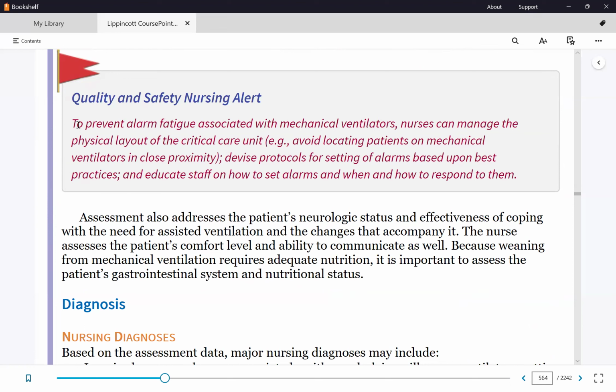During my time when I went to school, the vents were still capable of being... you can disable the alarm, and we can, because sometimes we're tired of hearing it. It's like the boy who cried wolf, it keeps beeping, but there's nothing wrong. The patient's absolutely fine. So we were able to disable the alarm. Now, modern vents, you cannot do that anymore. So you either have to fix the problem or it will never stop beeping.